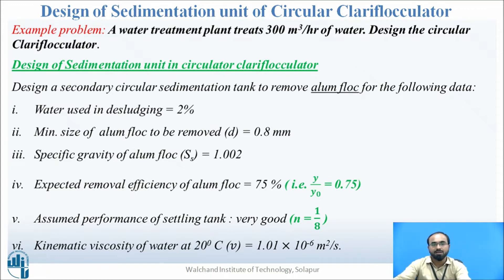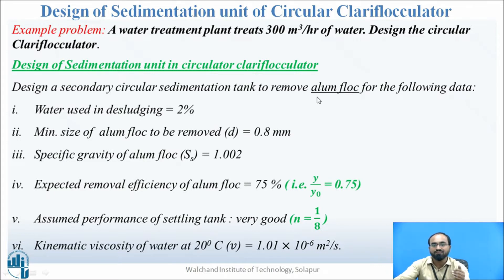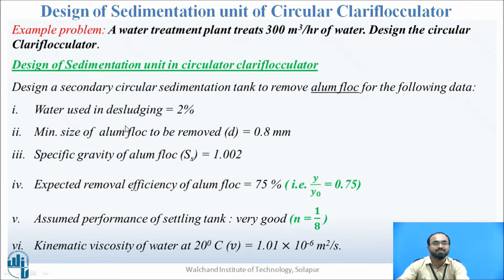We are now going towards the design of the sedimentation unit. We need some additional information from the problem statement. We are designing a secondary circular sedimentation tank to remove alum flocs — alum because it is the coagulant added before the flocculation unit. Water used for desludging will be 2 percent of discharge. The minimum size of alum flock to be removed is 0.8 mm (small d). Specific gravity of alum flock (SS) is 1.002.